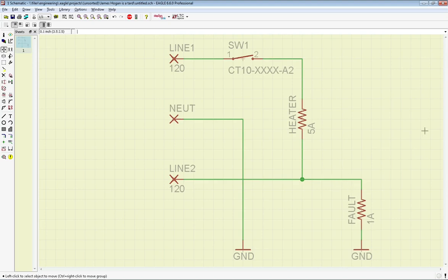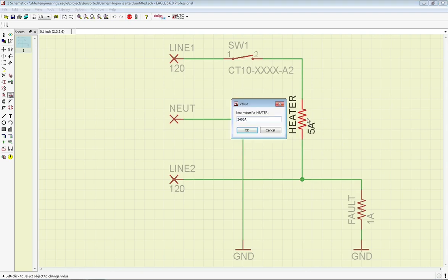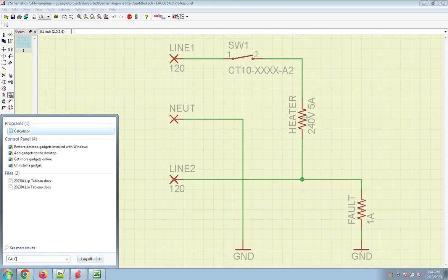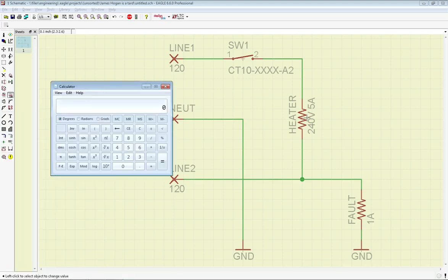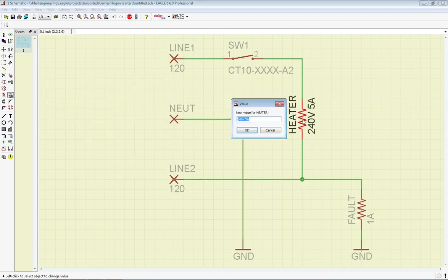So you're suggesting that if we... Well, first off, let's talk about this fault right now, okay? We've got 120 volts there and 120 volts there, so we've got 240 volts across this heater. It has 240 volts across it and is pulling 5 amps. Ohm's law is very clear on that. If we've got 240 volts across something and 5 amps going through it, then this heater is 48 ohms. I can type it. Symbols that way.